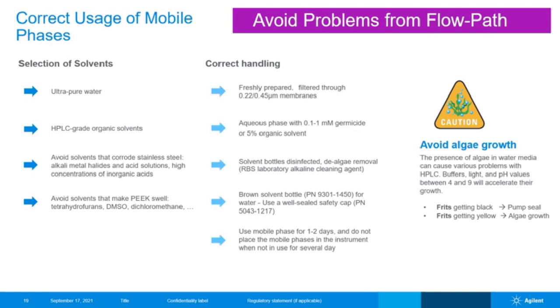Buffers, light, and pH value between 4 and 9 will accelerate their growth. Using freshly prepared and filtered water reduces the occurrence. Including a small percentage of organic solvent in the water phase and using the brown solvent bottles reduces consequently the risk of algae growth.